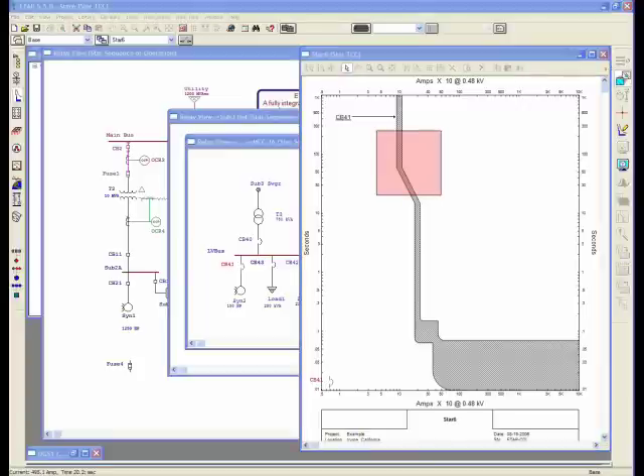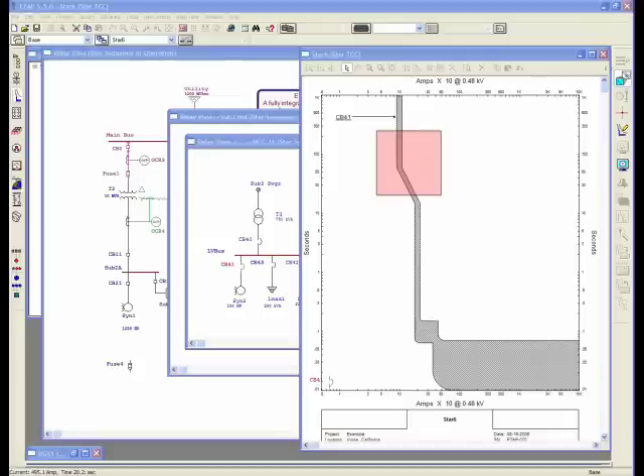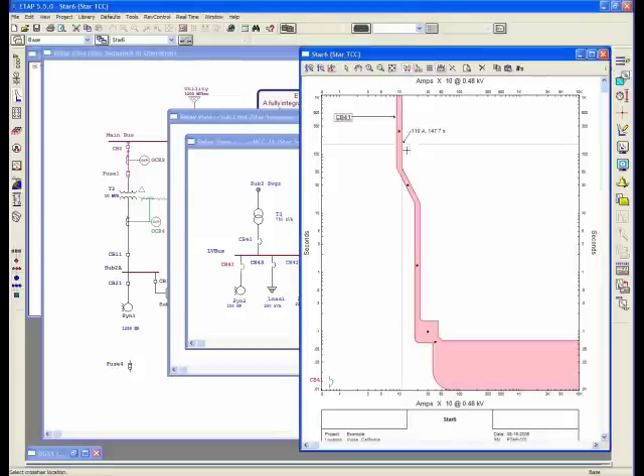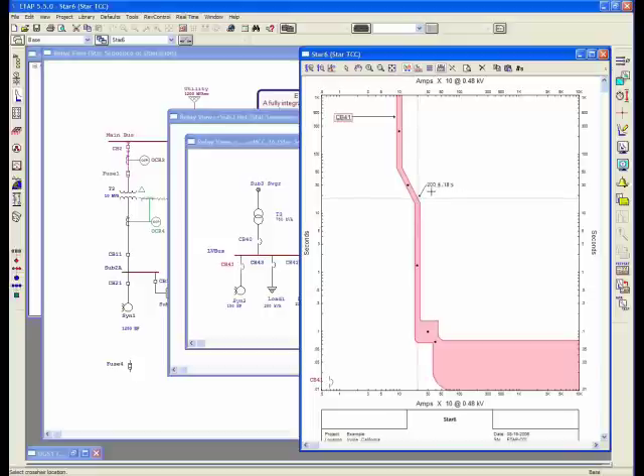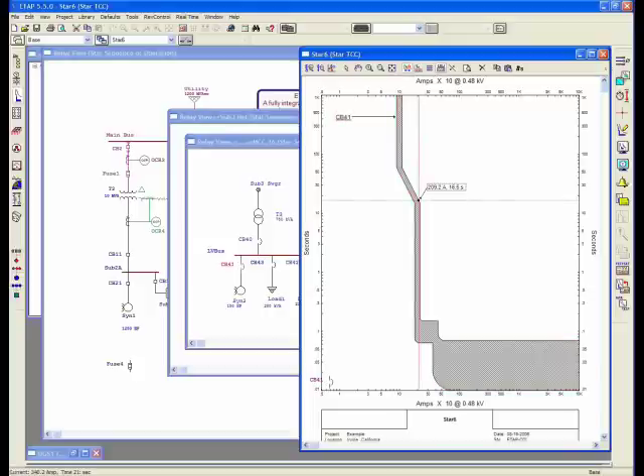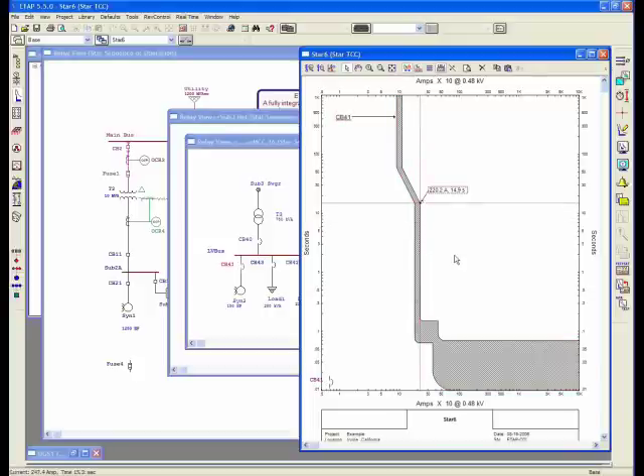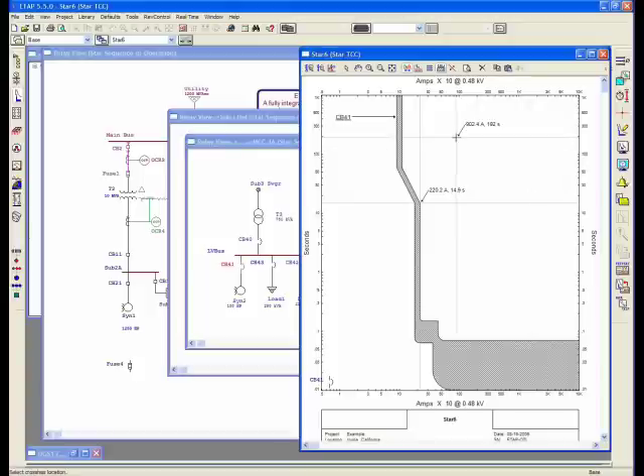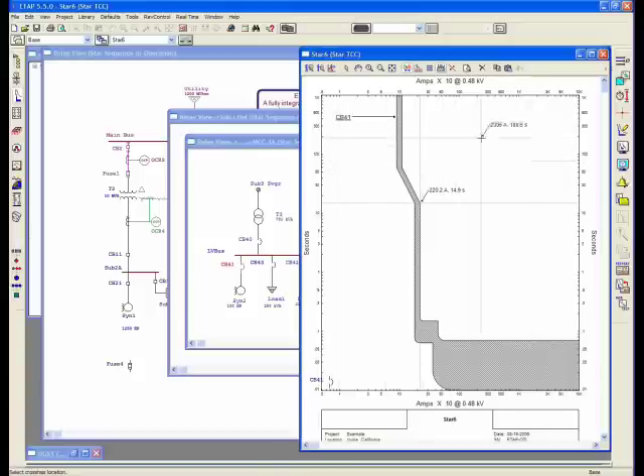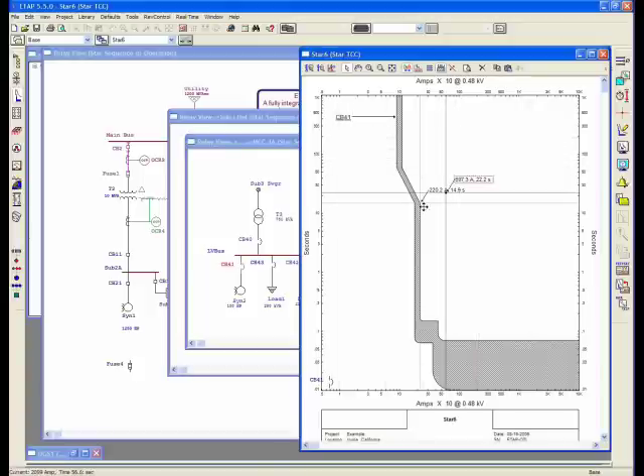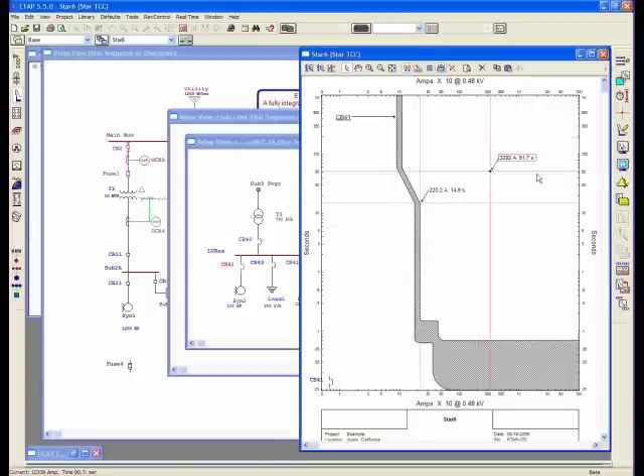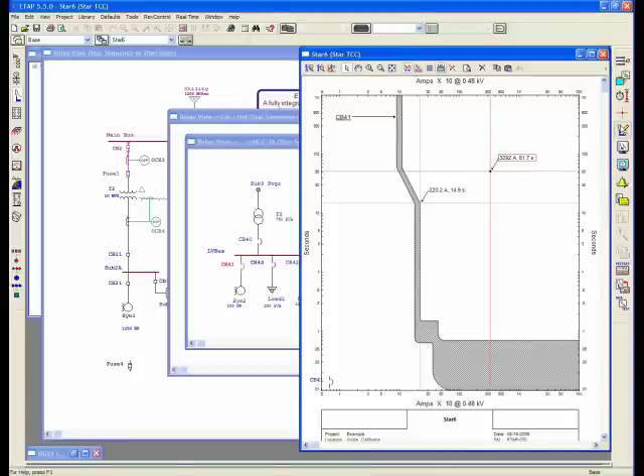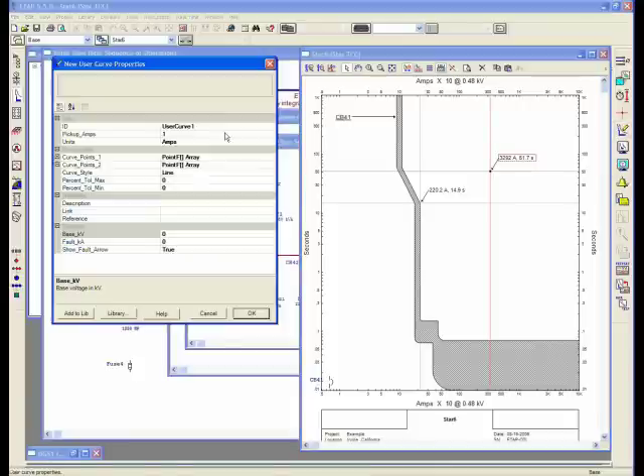The other tools provided are zoom to view. There are a number of tools here. Crosshairs, for example, you can select on the crosshair and you can drag the curve on either the minimum or the maximum clearing curves, and it gives you the time. You can leave that in there and actually move it along at any point. You can print with that information. You can drop a free-flowing or non-linked time-current curve crosshair which gives you the current and time.